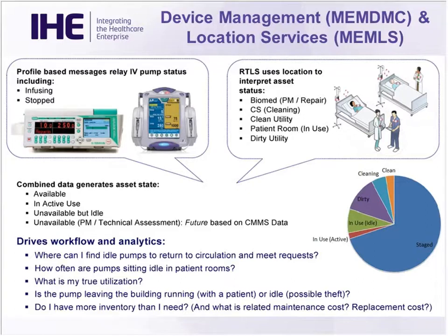In the current cycle, we're paying attention to the communication to the device. Initially, we just focused on communication of observations and alerts from the device. We're now creating a mechanism whereby you can communicate to the device for things like pausing alerts, for clearing infused volume status once that gets recorded. So we're looking at good opportunities in the future to expand MEMDMC.